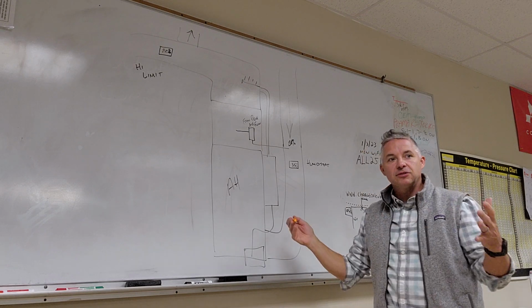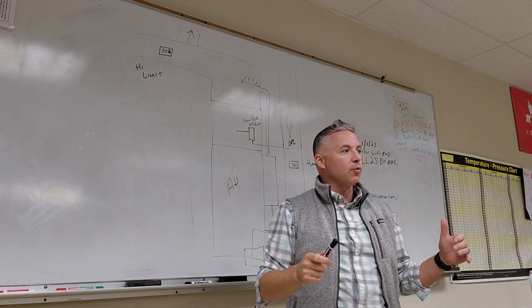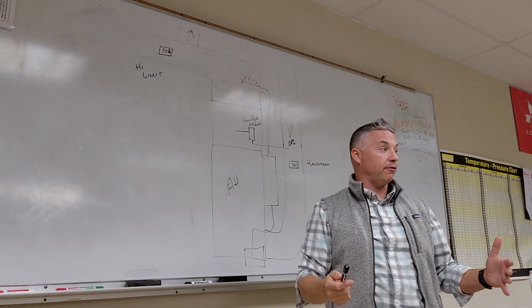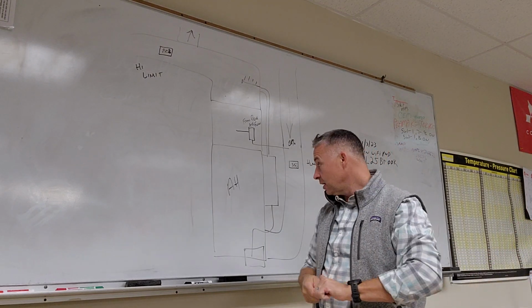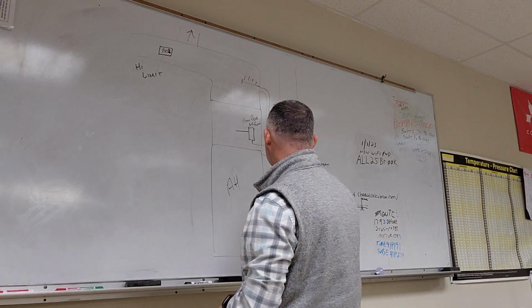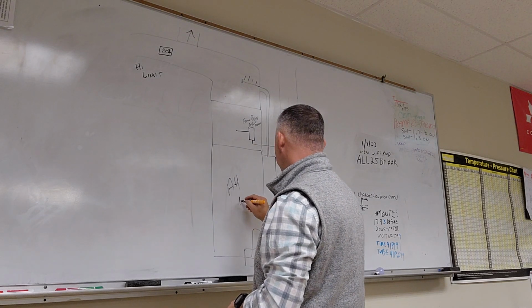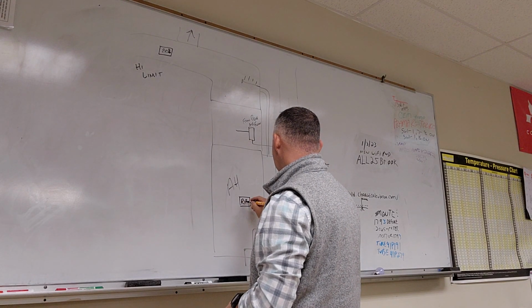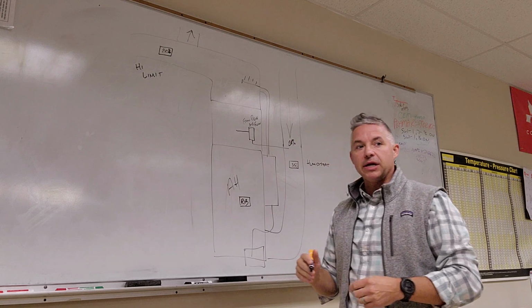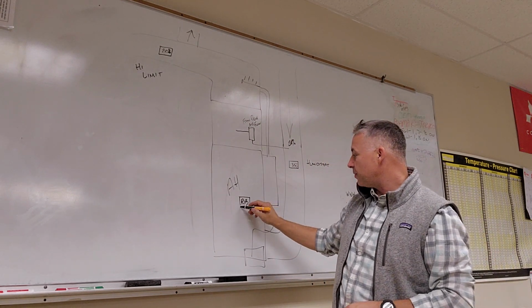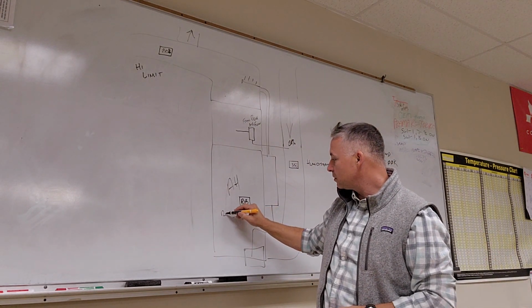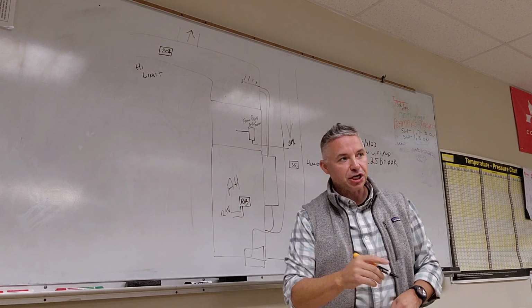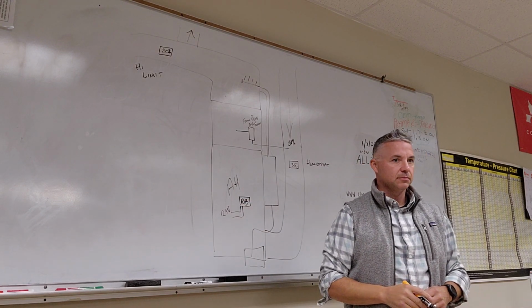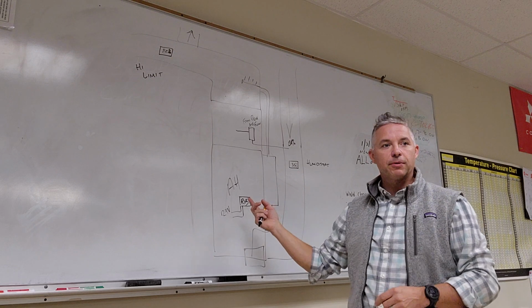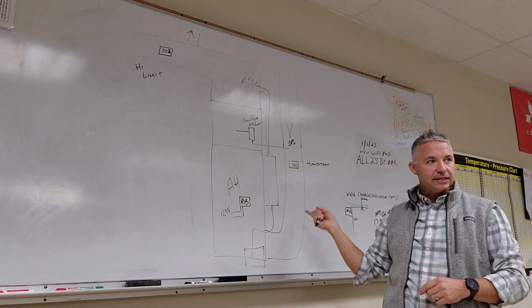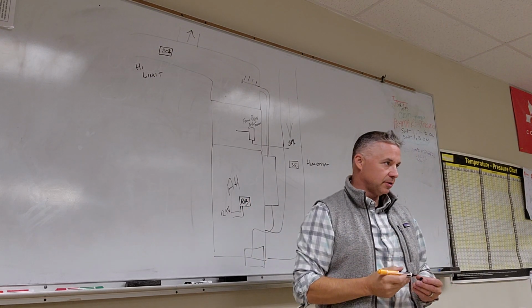So here at Alliance, when ECM motors became the norm, we decided to do another layer of safety. And we started installing a rib relay. And I'll just draw it in here. A rib relay that is energized on the coil side, 24 volts, from the fan circuit. Okay, and then we use the normally open contacts to wire it in series with all the rest of the controls.